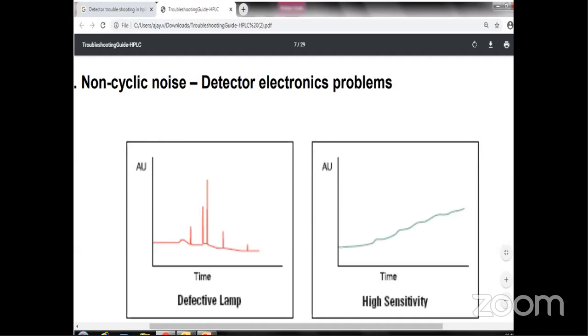So you can see the first slide, which is in red color. I'll explain this practical challenge which we faced during one of our lab operations: there is electronic noise observed, and I told you that the environment where we keep the detector is also important. It's not coming from any solvent or sample or from any column leak or air entrapment. It's the environment which will give such a spike. If you find very sharp peaks like a pin in your chromatography at any time, you can easily identify that it is not because of the system, the detector, or the sample you prepared. It's because of the environment where you have kept your detectors. So maybe you can discuss with your engineering department whether there is any specific voltage or any vibrations which can lead to such noisy baselines.